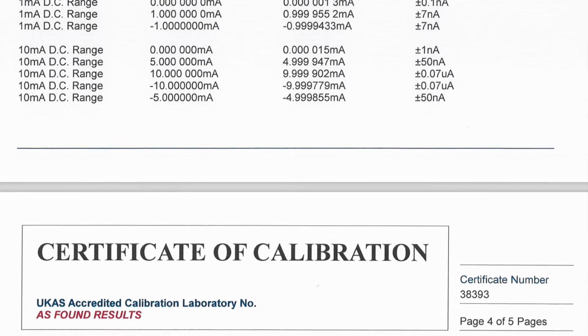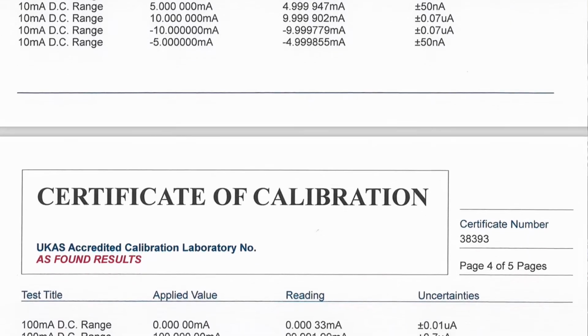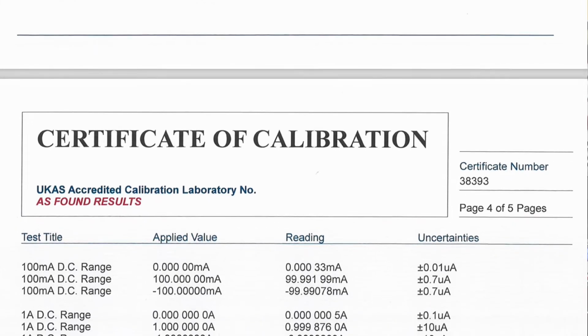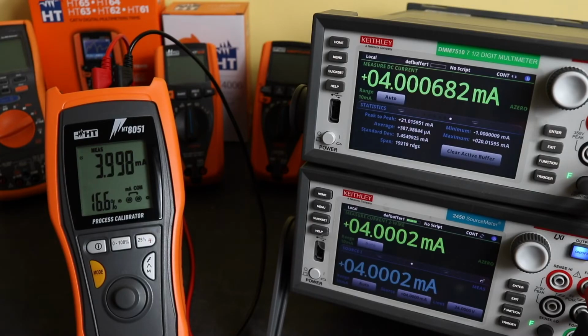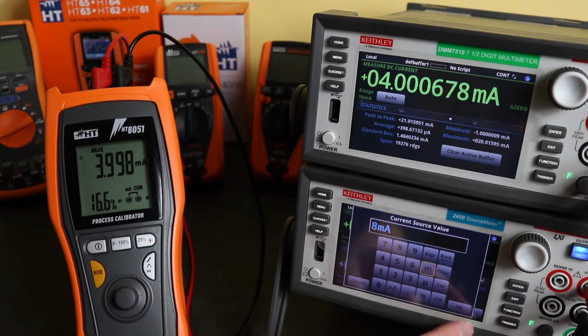Now I do actually keep an independent UKAS calibration on both these instruments, so I know they are actually more accurate than that, so I can get a good idea of how well this instrument is operating by using these instruments. And you see at this moment in time we are demonstrating current measurement on the HT8051. We're injecting 4.0002 milliamps, which is being read as 4.0006 on the DMM7510 and 3.998 on the HT8051. And we'll go up to 8 milliamps and see how we do.